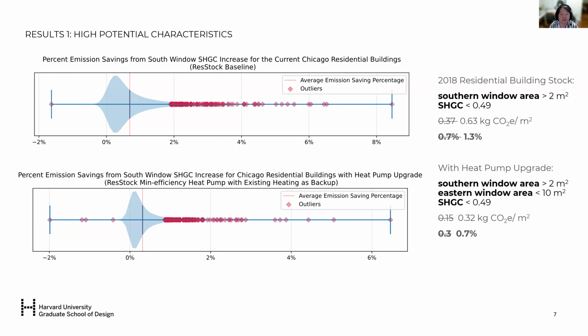There are some key characteristics to point out. As you can see in the distribution, some buildings can be negatively impacted, in this case by less than 2%. But some buildings can benefit a lot more, for example over 8% or 6%. Those buildings have common features such as a large southern window area, which makes sense because we're only modifying the south-facing window solar heat gain in this case study.